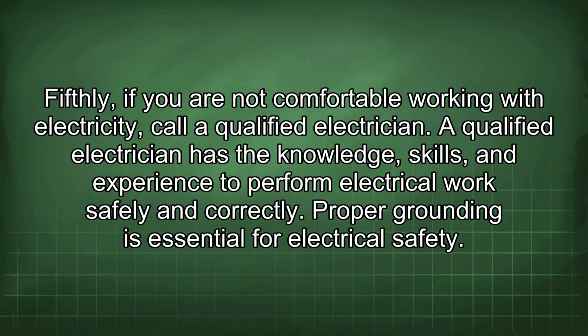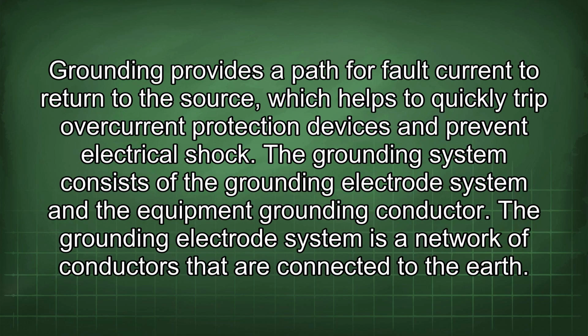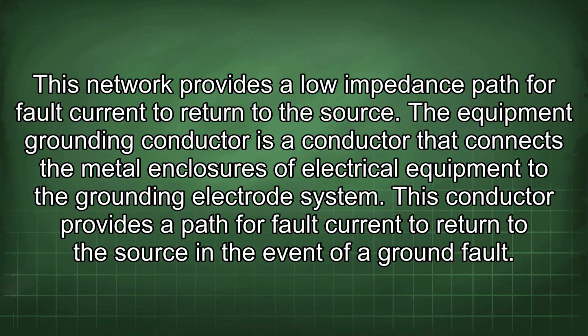Proper grounding is essential for electrical safety. Grounding provides a path for fault current to return to the source, which helps to quickly trip overcurrent protection devices and prevent electrical shock. The grounding system consists of the grounding electrode system and the equipment grounding conductor. The grounding electrode system is a network of conductors that are connected to the earth. This network provides a low impedance path for fault current to return to the source. The equipment grounding conductor is a conductor that connects the metal enclosures of electrical equipment to the grounding electrode system. This conductor provides a path for fault current to return to the source in the event of a ground fault.